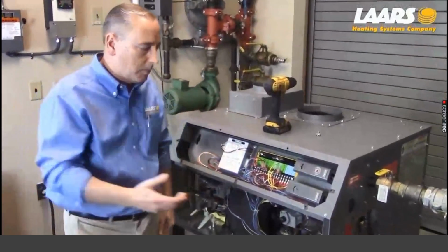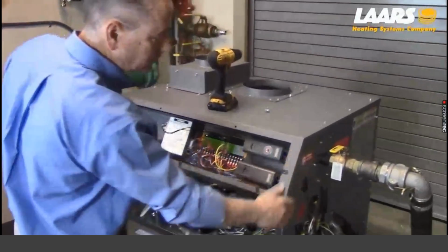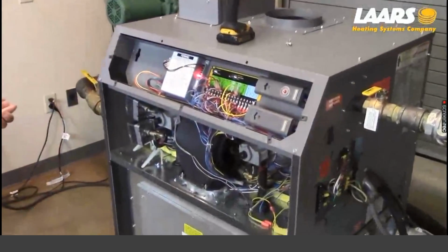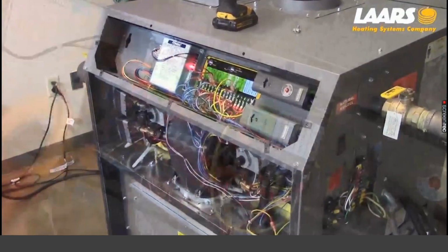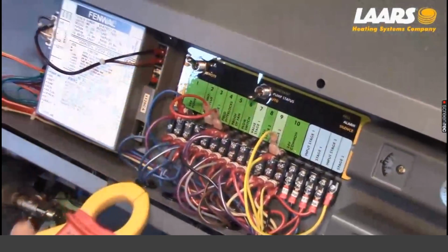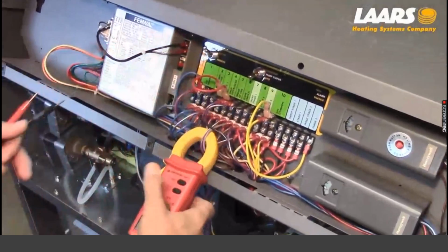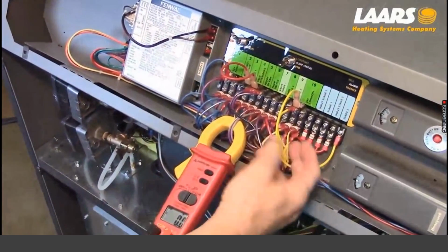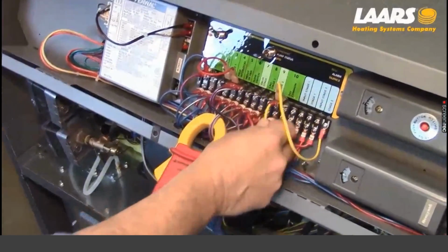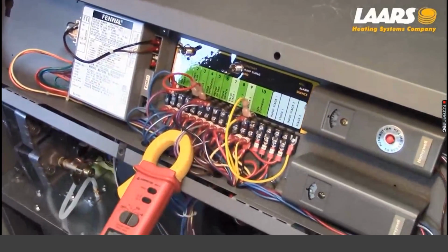Okay, we're going to troubleshoot the safety circuit. I'm going to start by powering up the boiler, and then we're going to walk through the terminal strip. All right, so I've got my voltmeter hooked up to voltage. I'm just going to clamp it here to hold it in position so you can see it. I want to mention to you, all of our yellow wires here are 24 volt common.